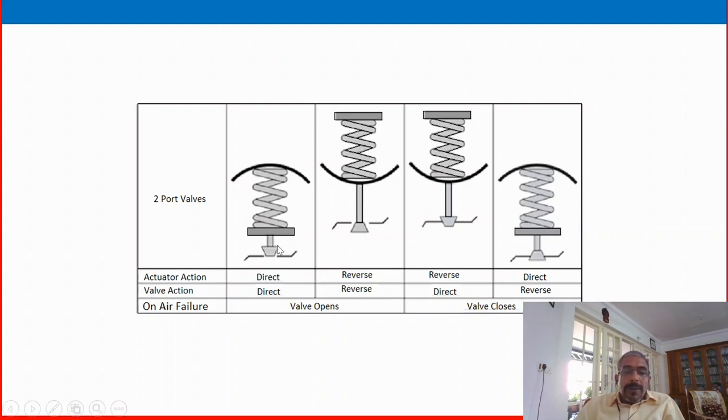What will happen? Automatically in these two cases, direct-direct and reverse-reverse, the valve will go to the open position. That is the concept, that is the design. But in the other cases, reverse-direct and direct-reverse, in case of air failure, the valve will close. You will understand, it will take some time, but after one or two slides of this video you will get a better idea. Why the valve opens or closes on air failure, and why it is important, we will discuss.